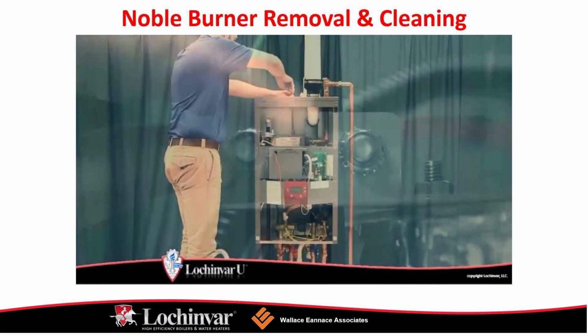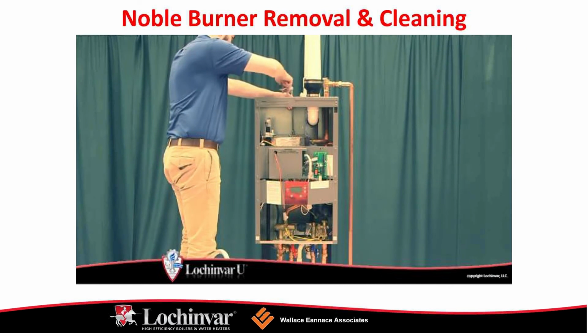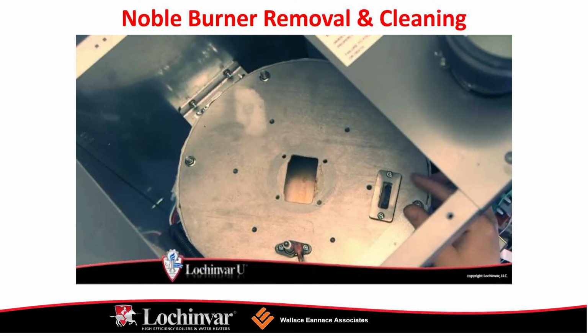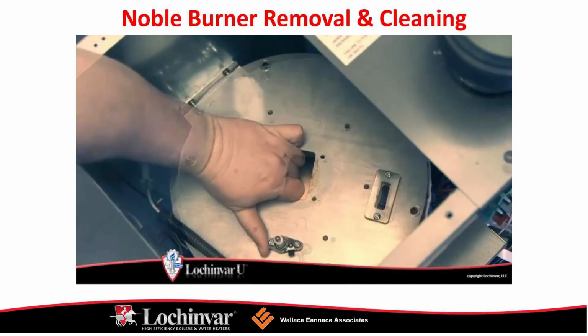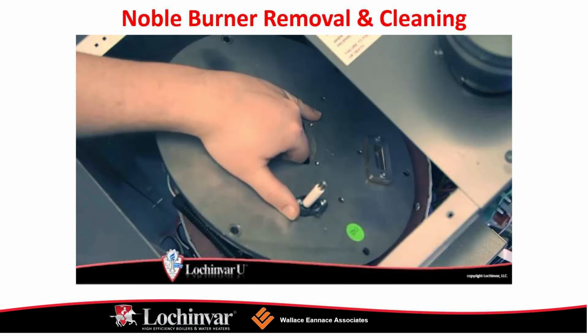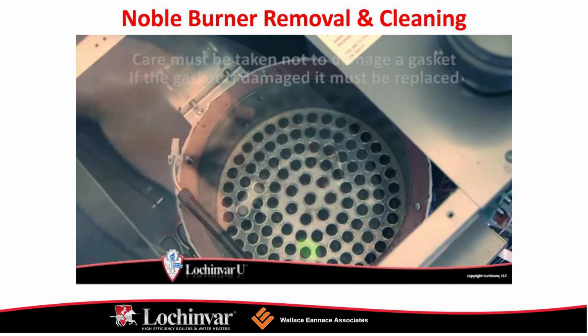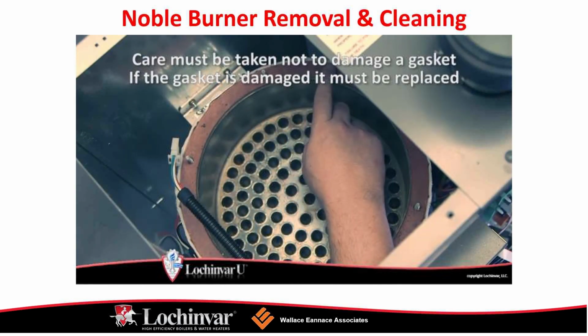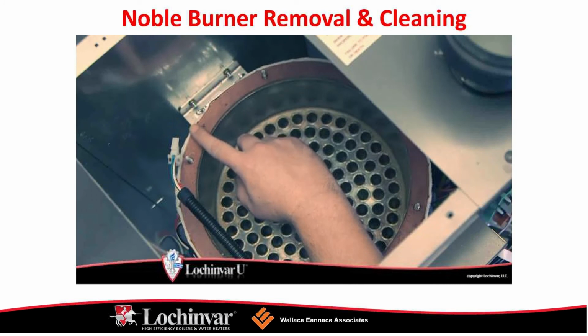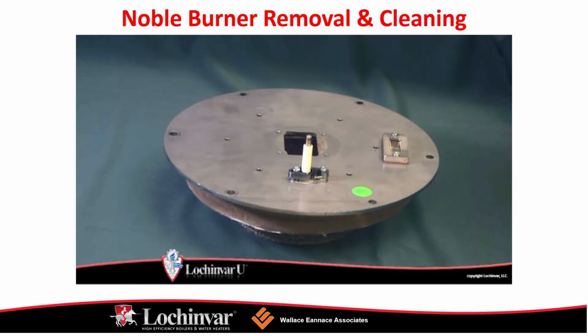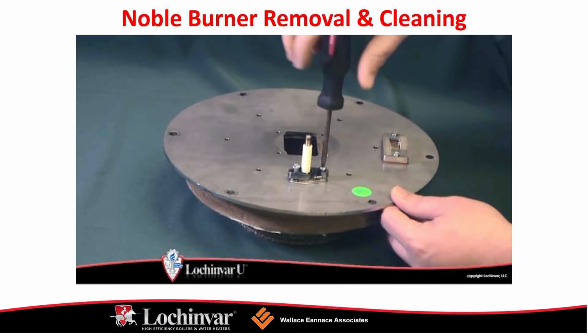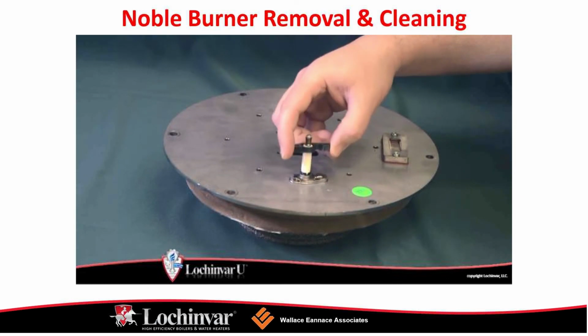Then locate and disconnect the two wiring harness connections to the fan assembly. And locate and remove the wiring from the spark igniter and ground terminal. Now, using a 3mm Allen wrench, remove the 4 screws that secure the gas valve flange to the gas valve assembly. Loosen the union that secures the gas valve adapter to the Venturi and remove the gas valve from the unit.